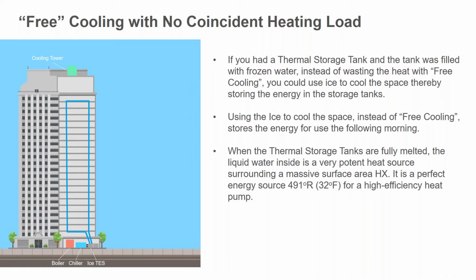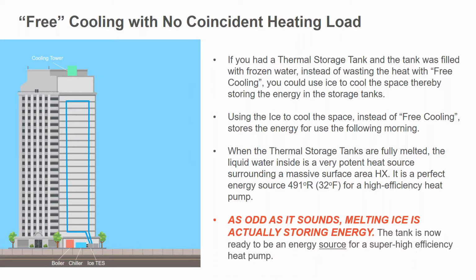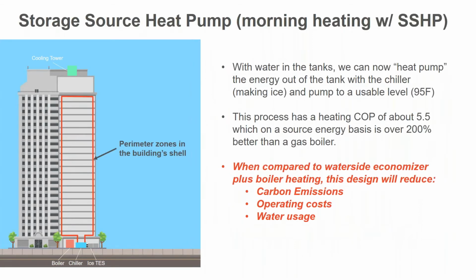And so you have the tanks cooling the core of the building on the winter afternoons when it's overheated, and you just have this ice, and you're now storing today's waste energy. And what are you storing it for? You're storing it for tomorrow morning's warm up. So as odd as it sounds, melting ice is storing energy, and it can be a real source for a heat pump, and that heat pump is really a chiller.